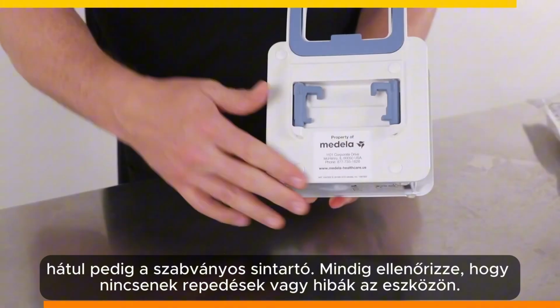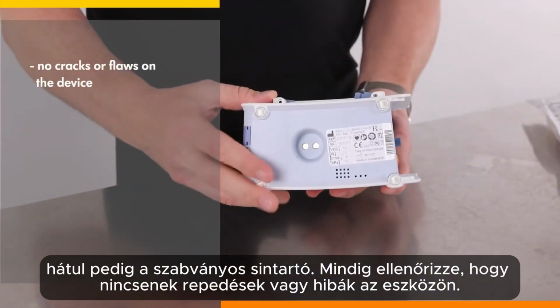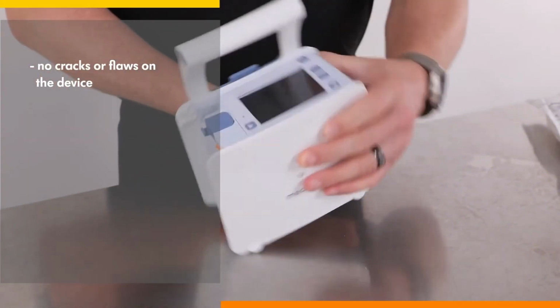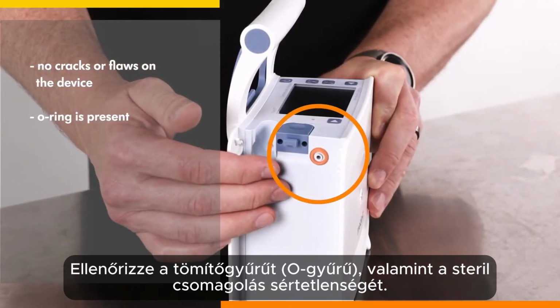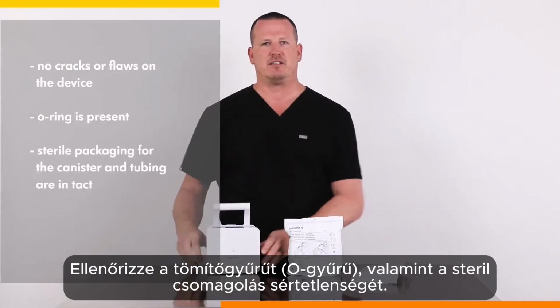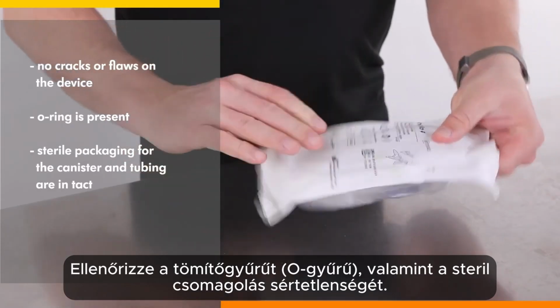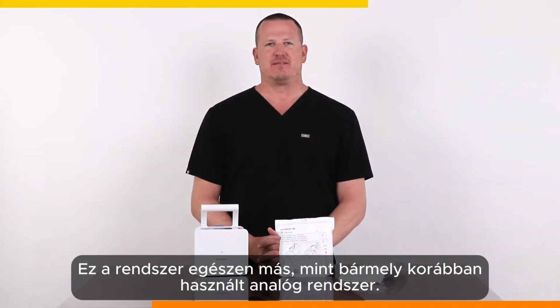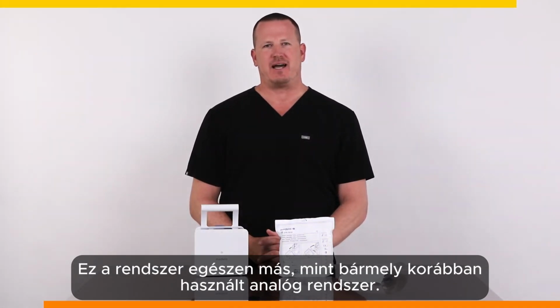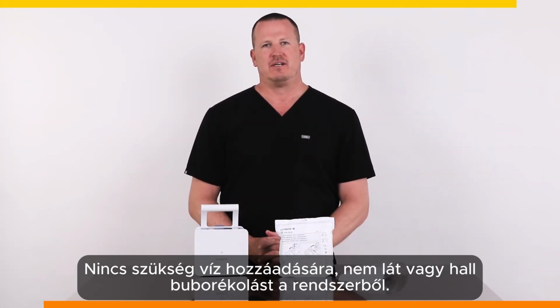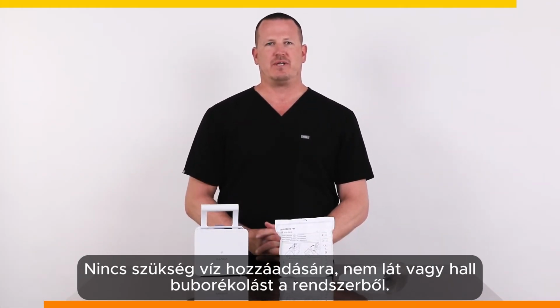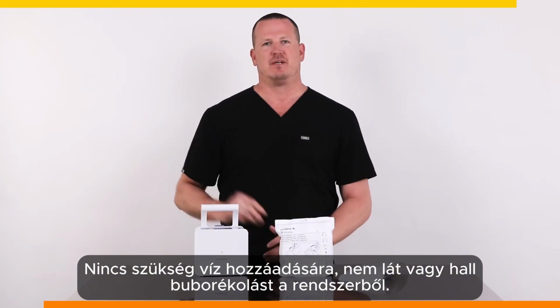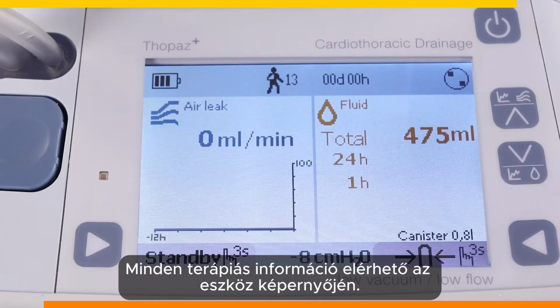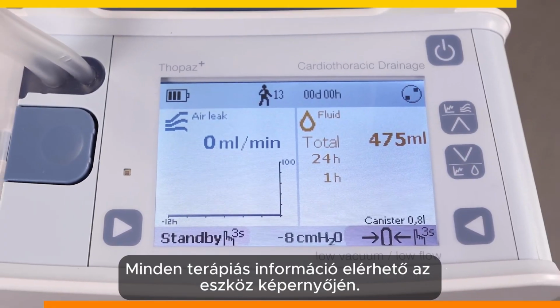Always get into the habit of checking everything first, making sure there are no cracks or flaws on the device, make sure the O-ring is present, and make sure that the sterile packaging for the canister and the tubing are intact. This system is unique and quite different from any analog system that you have been using. There is no need to add any water, and you will not see or hear any bubbles from the system. All of the therapy information will be available digitally on the device screen.